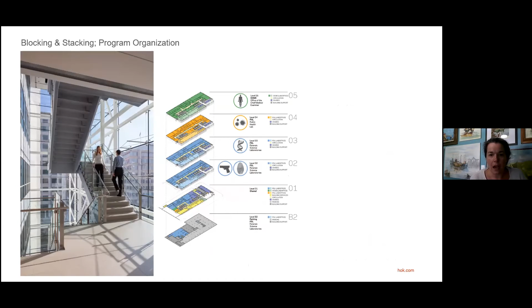One of the really interesting things about thermal programming and blocking and stacking in this type of building is that it's internal load driven — 100% outside air — so fan energy and plug load energy really drive the needle. In this case, the space with the highest air change rate requirement was the morgue, so we decided to put it on the top floor closest to the penthouse, to reduce the duct run and the fan energy required to ventilate it.